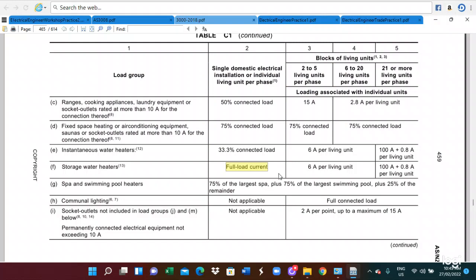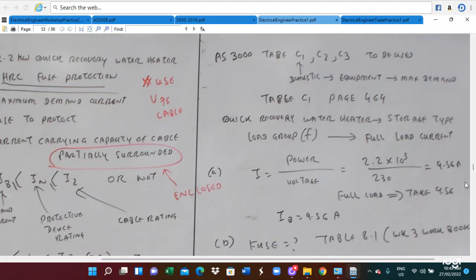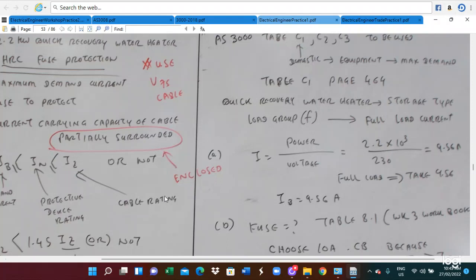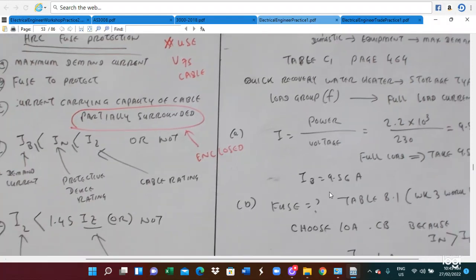The maximum demand is equivalent to the full load current. For a storage water heater, the full load current is calculated as: kilowatts divided by the supply voltage. So 2.2kW × 1000 / 230V = 9.56A. Therefore, IB, the maximum demand current, is 9.56A.